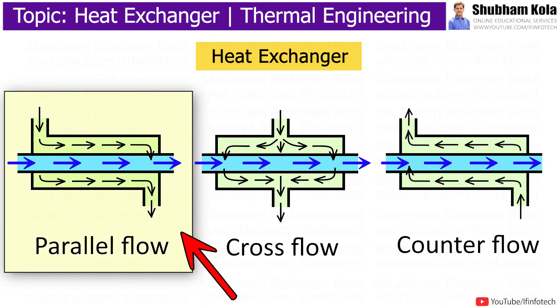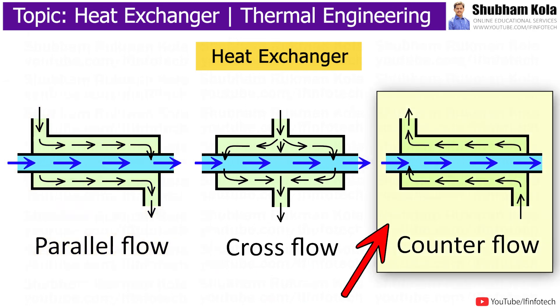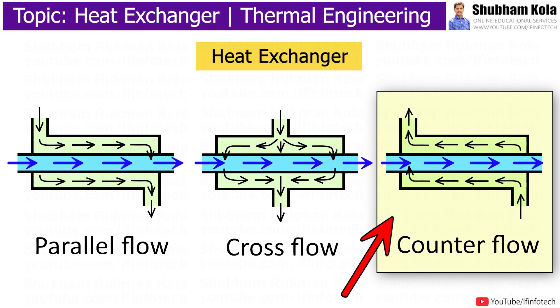Parallel flow occurs when both shell side and tube side mediums enter the heat exchanger from the same end and flow to the opposite end. In counter flow heat exchangers, the two flowing mediums flow in counter direction to each other — each enters at opposite ends and is discharged at opposite ends. Counter flow heat exchangers are the most efficient type of heat exchanger.